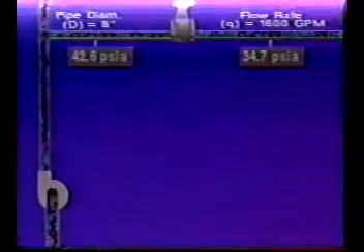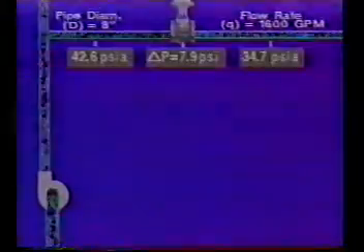The control valve we'll be sizing is to be used in a river water system that provides cooling for a process. Data that's been collected indicates that the valve will be located in an 8-inch Schedule 30 pipe. The maximum flow rate to the process will be 1,600 gallons per minute. Upstream pressure will be 42.6 PSIA, and downstream pressure will be 34.7 PSIA. So differential pressure across the valve is 7.9 PSI.